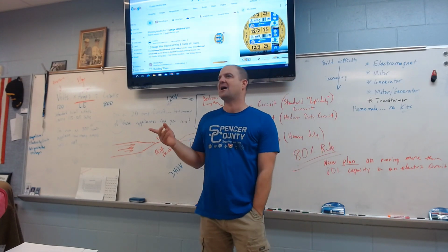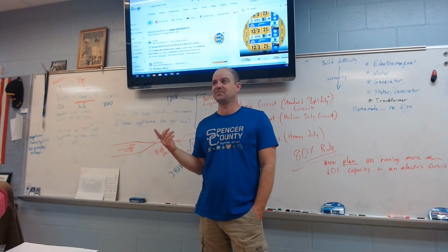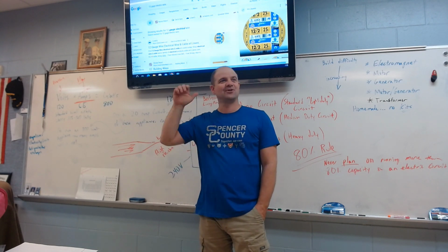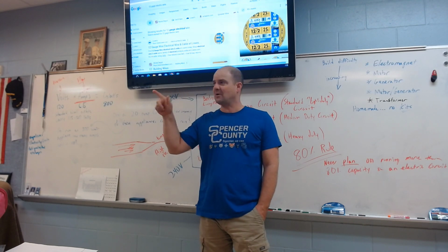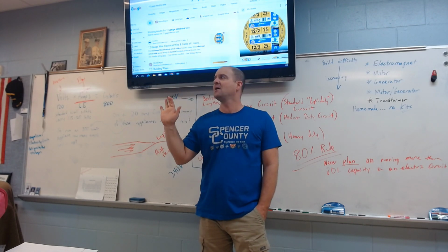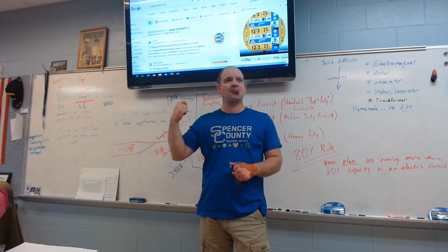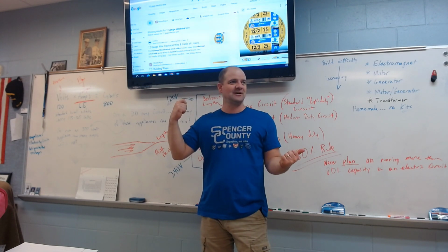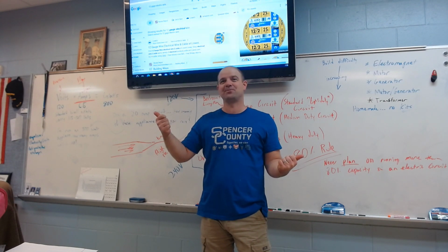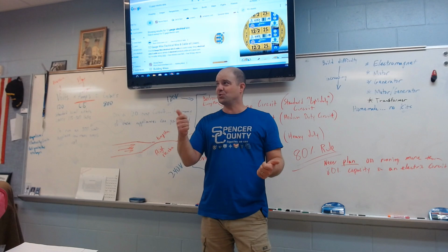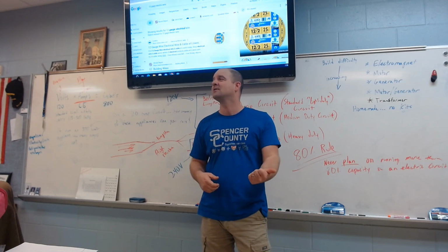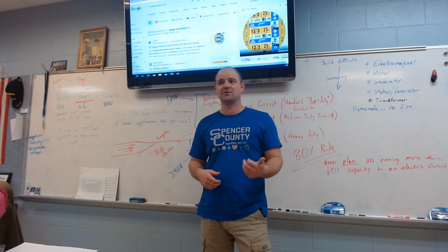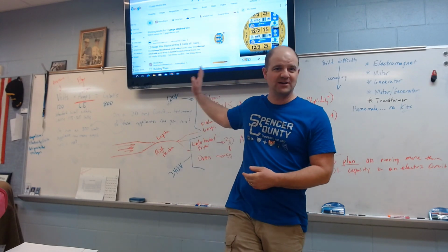Bathrooms are another place where stuff gets tripped a lot because of curling irons or hair dryers. Ladies, a couple of guys with long hair in here. Anybody try to run a hair dryer and somebody else using the curling iron? Does that trip it? Oh yeah, because if it's a 15 amp circuit, and you're running 1,000 watts for your curling iron and 1,500 watts on high for your blow dryer, you're going to push past that 15 amps.